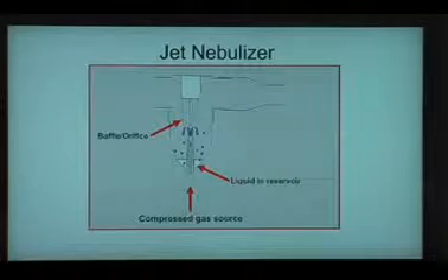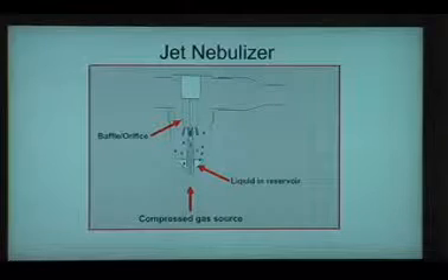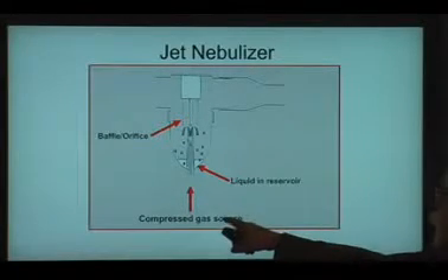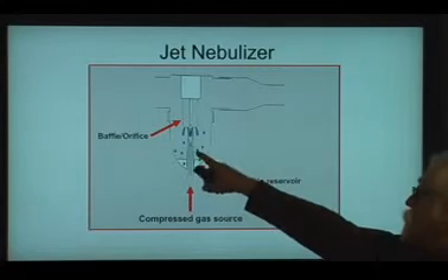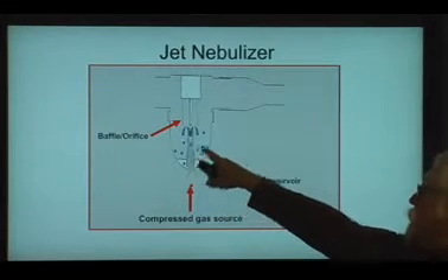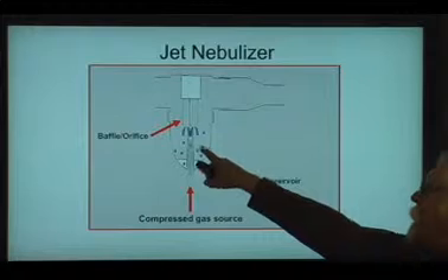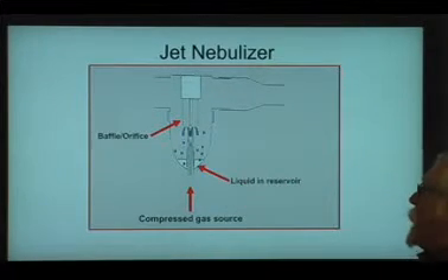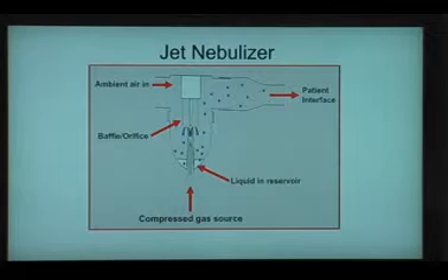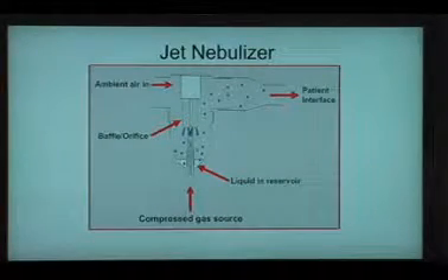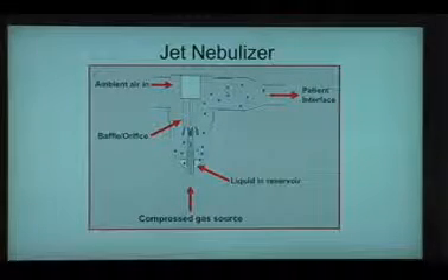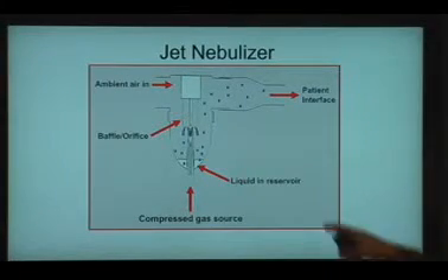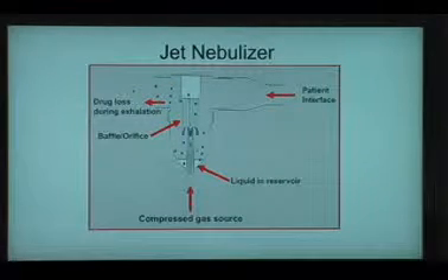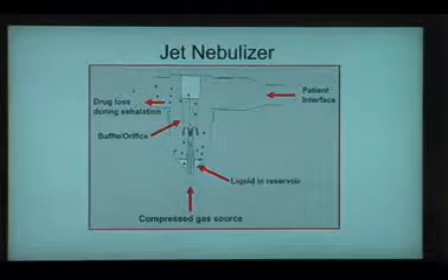So here is our friend the jet nebulizer that all of us, I'm sure, should be very familiar with. These rely on a compressed gas source. The compressed gas source draws a liquid from a reservoir and blasts it against a baffle to produce an aerosol, and then the patient inhales that aerosol. But for many, not all, nebulizers, the aerosol is produced not only during the time that the patient's inhaling, but is also produced while the patient's exhaling.